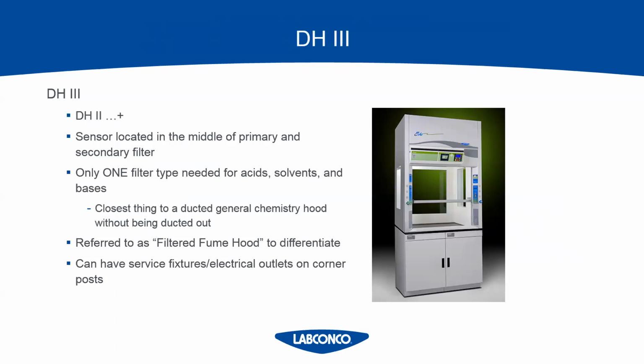Size-wise, the hood and filters are actually larger too. Each filter is about 3 times the size of a DH1 and DH2 filter. So just by sheer volume, these filters have more carbon, and therefore the filters will last longer. This hood has corner posts, as you can see, so you can install service fixtures and electrical duplexes. So it's as close as you can get to being a general chemistry fume hood without ducting out. And it also has a fully functioning sash that slides up and down, unlike the other enclosures that have a sash that lifts towards the user like a hatchback.